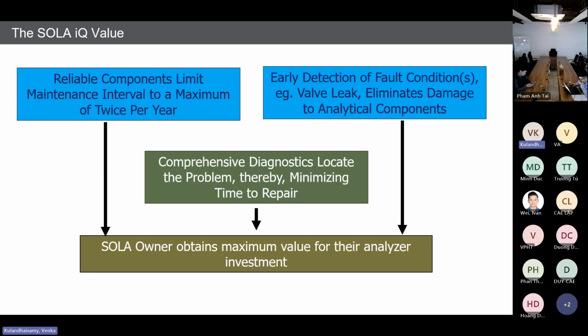But in SOLA IQ, there is a separate slide-down L bracket, so you no need to remove the bench totally from its position. Once you remove the lock, it will come automatically to the horizontal position. From there, you can do maintenance individually, part by part. But in SOLA 2, if you want to remove the photo detector, you need to remove the complete bench assembly, and only then can you remove it. But with SOLA IQ, it is very simple. You don't need to remove the whole assembly. If you remove just a few screws, you can replace the photo detector. Yeah, it is very simple to do the maintenance.